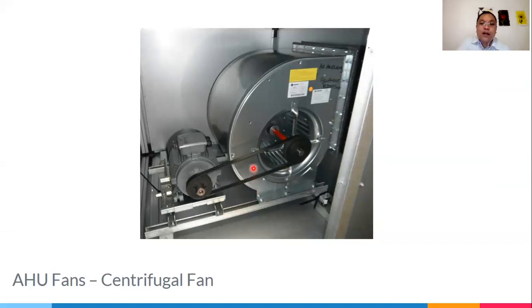Why do you need to do this? Why do you need to put a belt between the fan and the motor? You put a belt because the fan has a different rotation requirement than what the motor can give. For example, your motor runs at 1,444 RPM, but your fan only needs 1,000 RPM. So how do you reconcile the rotation speed of the two?